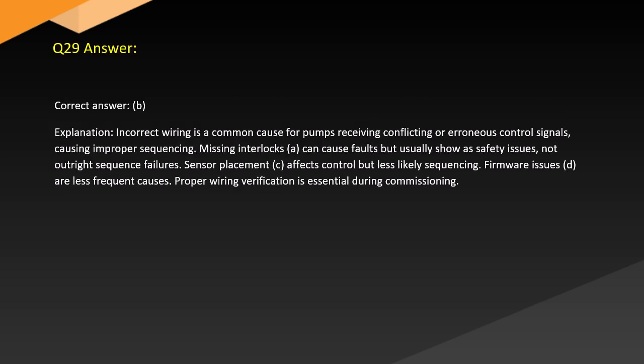Answer. Correct answer: B. Explanation: Incorrect wiring is a common cause for pumps receiving conflicting or erroneous control signals, causing improper sequencing. Missing interlocks, A, can cause faults, but usually show as safety issues, not outright sequence failures. Sensor placement, C, affects control, but less likely sequencing. Firmware issues, D, are less frequent causes. Proper wiring verification is essential during commissioning.